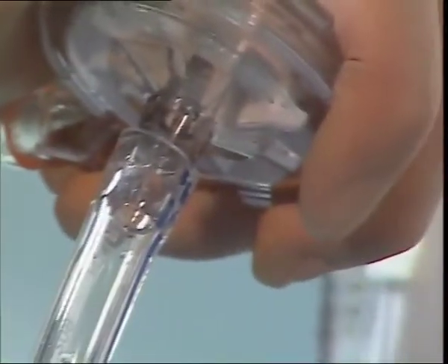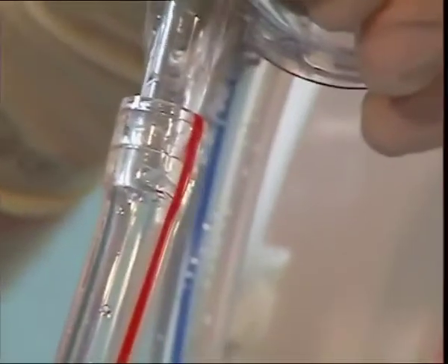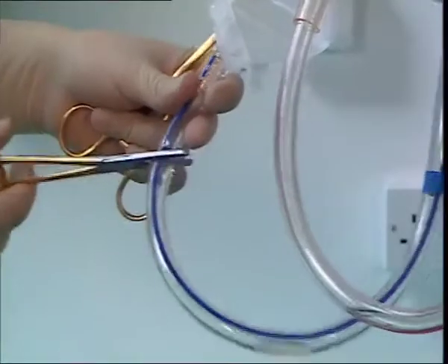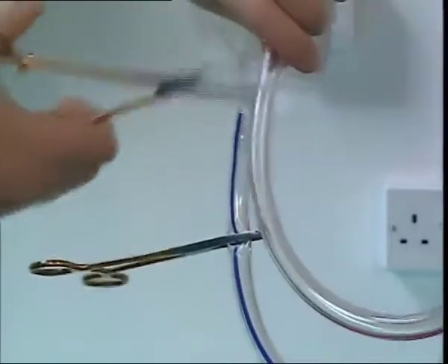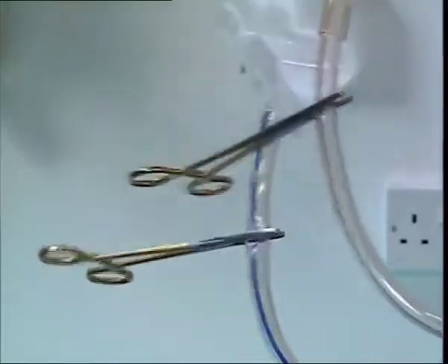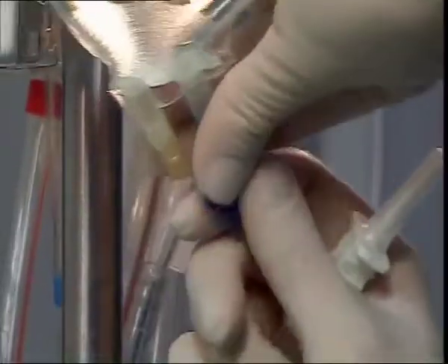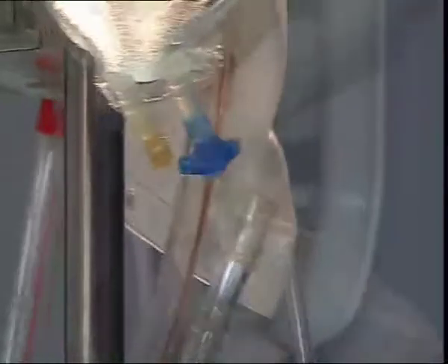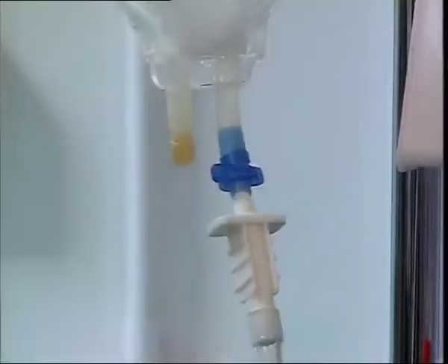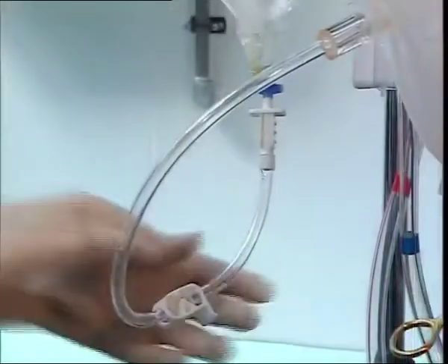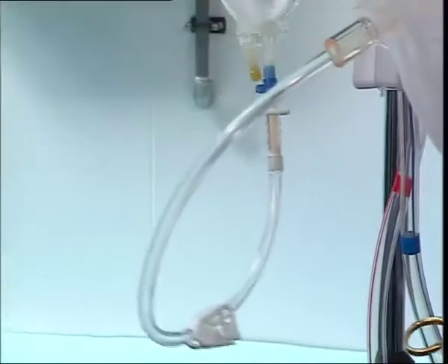Make sure that both tubes are pushed firmly over two barbs of the connectors. Clamp both blue and red tubes approximately 4 inches from the recirculation bag. Now attach the priming solution to the giving set and fill the recirculation bag.